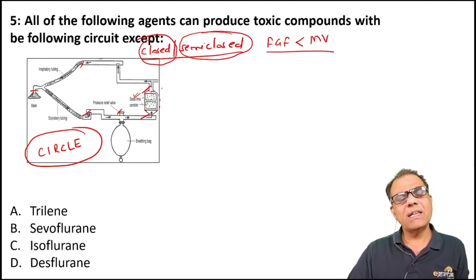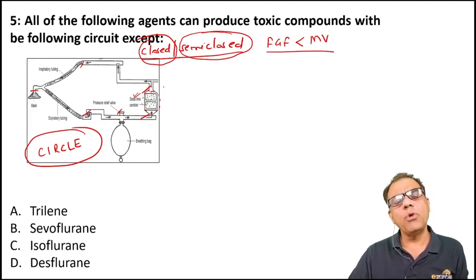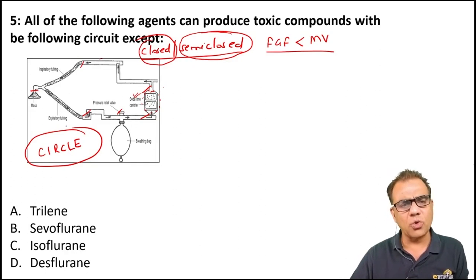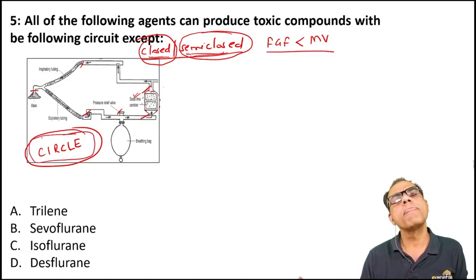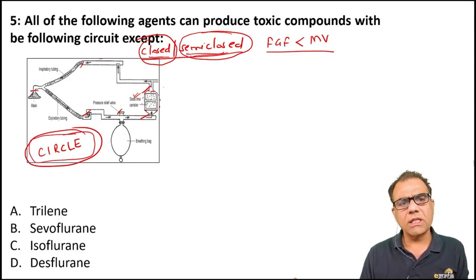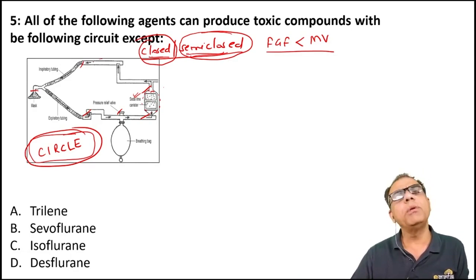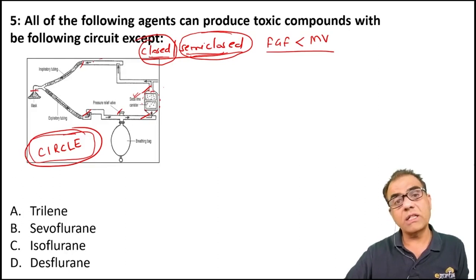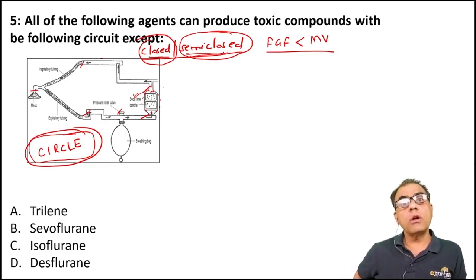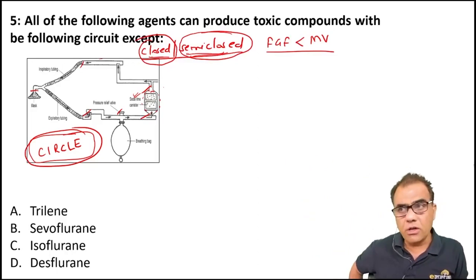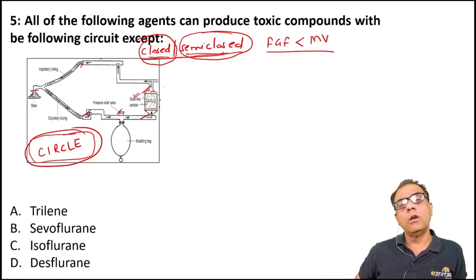So the advantage of the circle, when you compare it with the semi-open circuit, is this. Nowadays they avoid the terminology closed and semi-closed, and simply use circle system. The advantage of the circle system is that the same gases can be reused. So consumption of gases is less, so they become more economical, and since gases are not venting out into the atmosphere, there is less theater pollution.